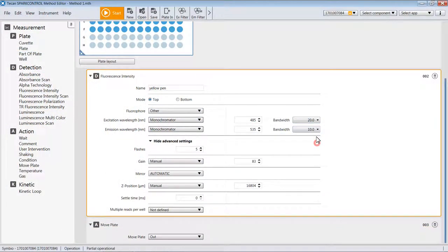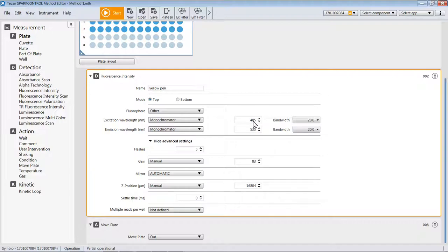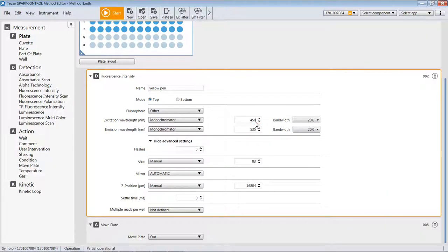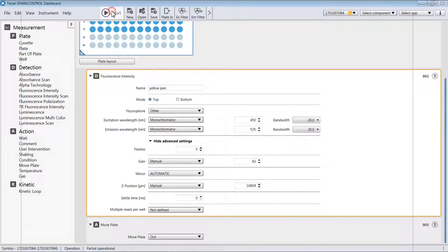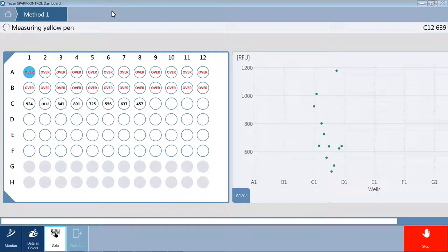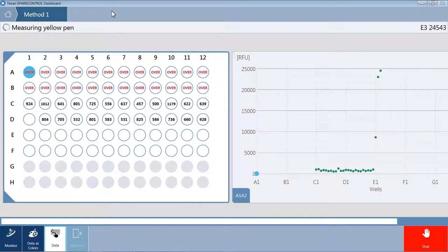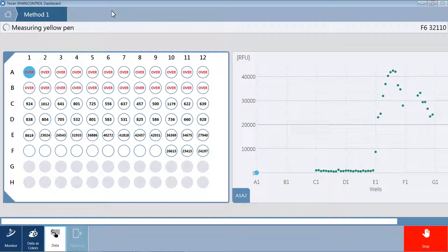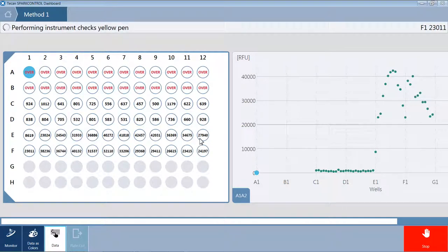Now, while keeping the gain and the Z position the same, I'll change the bandwidths back to 20, but then we'll switch the excitation wavelength to something that's more ideal for the orange highlighter pen and the yellow highlighter pen. A wavelength like 450 would work well here. The excitation of 450 is now driving all of the signals for the orange highlighter pen in A and B off scale, but in turn, it's also a more ideal excitation for the yellow highlighter pen, as you can see here by these increased signals.